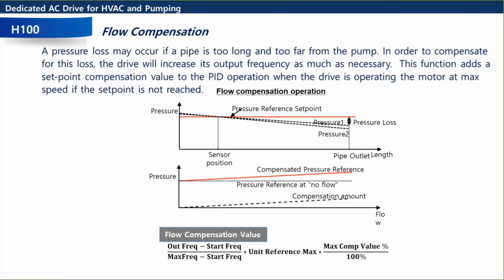It's pretty easy to use. What you do is you add in this parameter, which is called a set point compensation value, which is meant to cancel out the losses that you're assuming are in your system. As you can see here, you have a few different pressures because you're losing pressure, but you can have this compensated pressure reference, which is this line that's creeping up a little bit here. That's your set point compensation value. There's a formula. I won't bore you with the formula, but we've used this a few times for very, very large systems with long pipes.